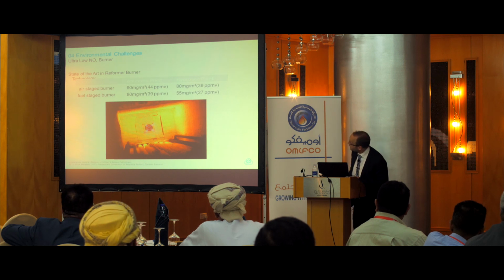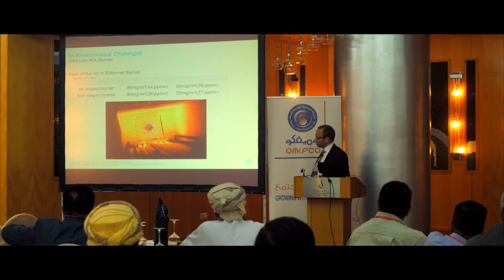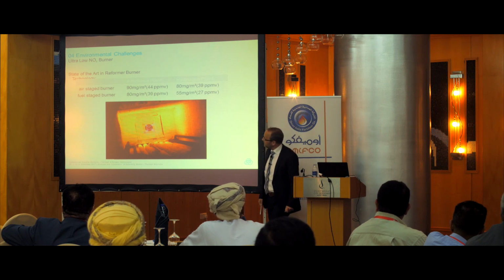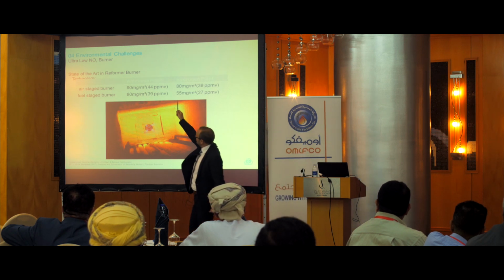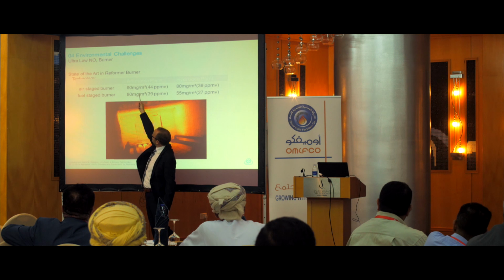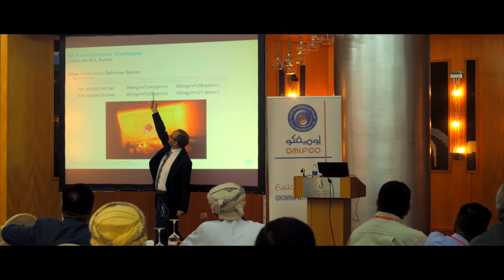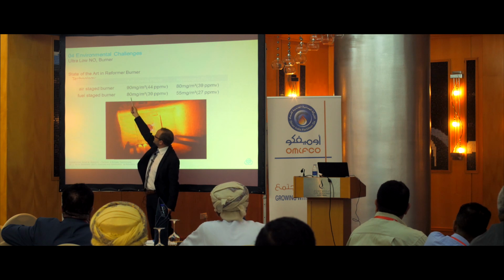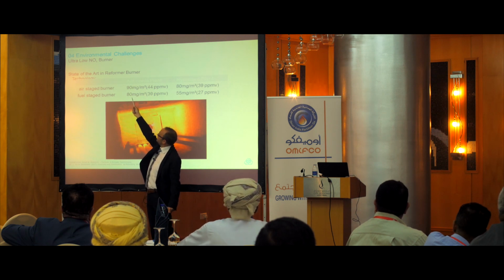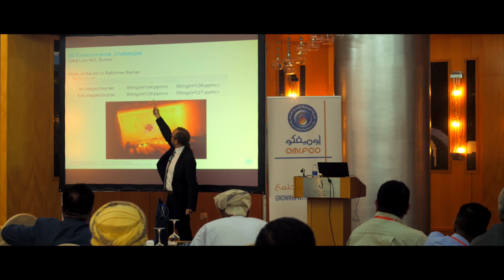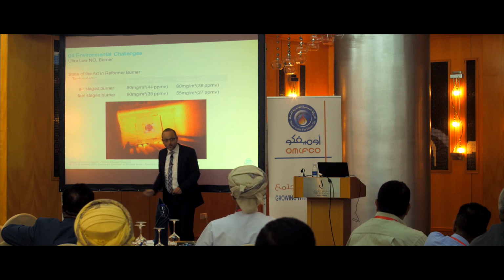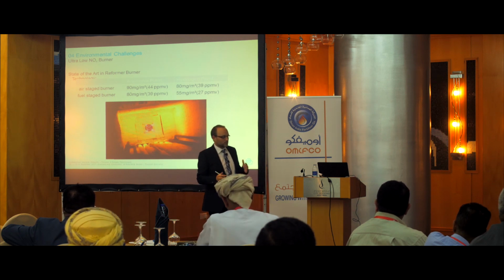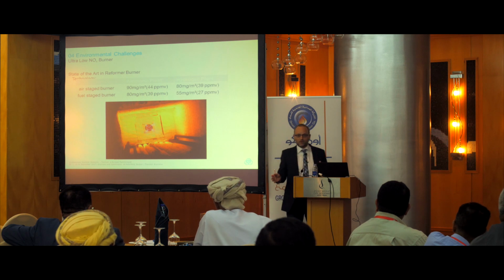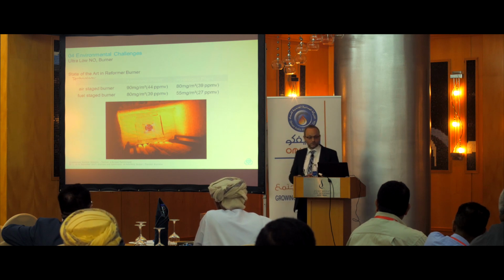So that is the state of the art in burner technology we have. For ammonia plants, basically air stage burners are going down to 90 milligrams, so around 44 ppm. Fuel stage burners, the best you can have actually is 80. That's around 39 ppm. Of course, this depends on the surrounding conditions like fuel and air temperature and so on.